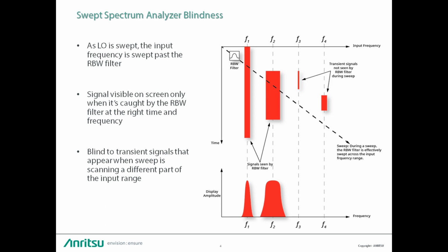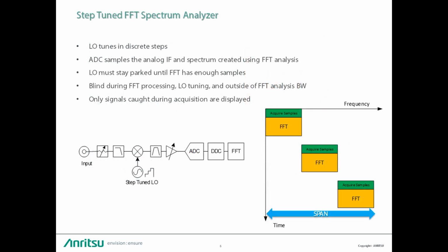The fact that some frequencies or carriers can't be seen on a spectrum analyzer represents one kind of blindness of a spectrum analyzer, as, depending on how often these frequencies occur, the spectrum analyzer may miss some information during a sweep. So let's see briefly why this phenomenon occurs.